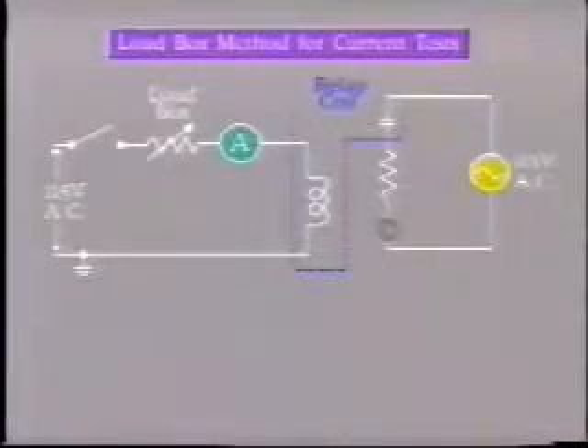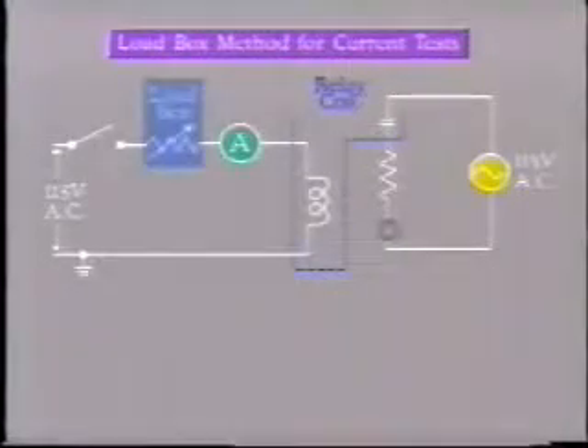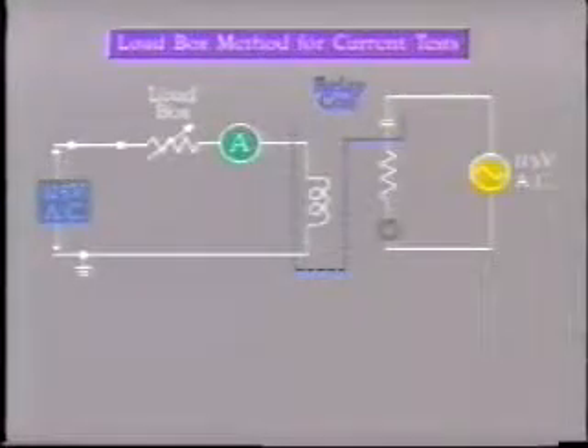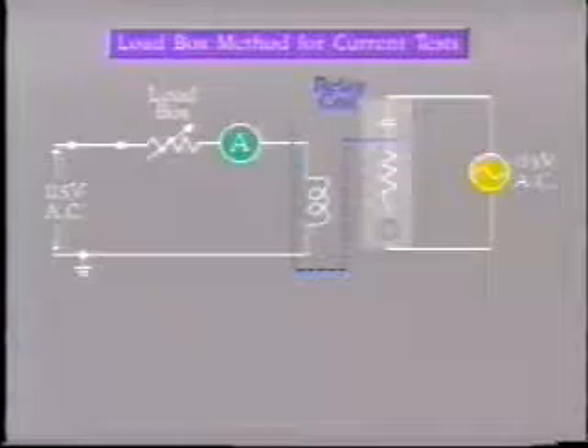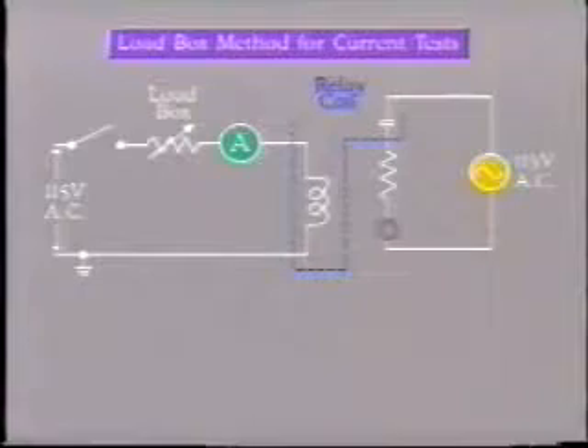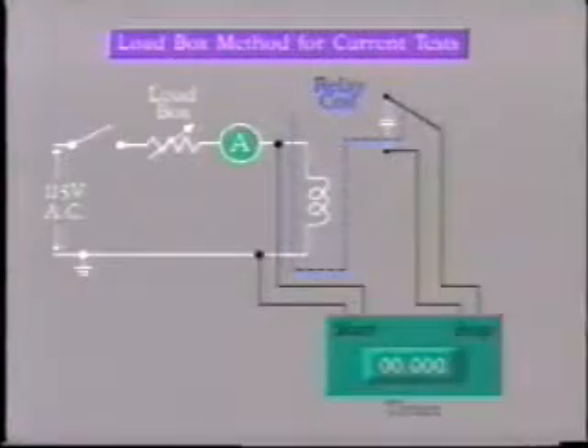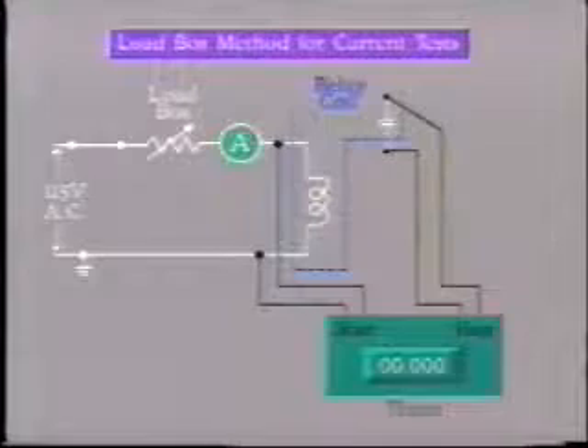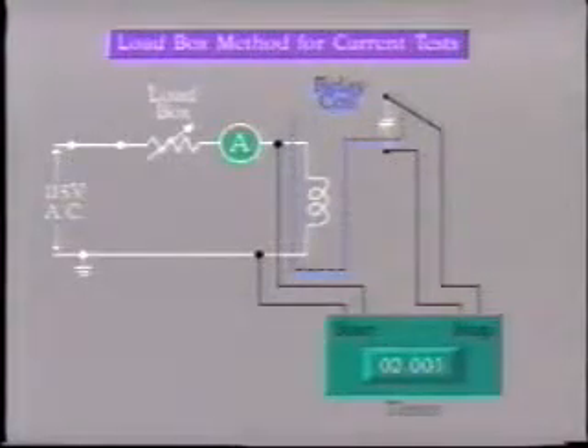First, variable current sources. A traditional method used to measure the pickup of an overcurrent relay is to connect a variable resistor called a load box and an ammeter in series with the relay, and to feed this from the station service 115-volt AC source. The relay's output contact is monitored by an indicating light. For time overcurrent tests, we can replace the indicating light by a timer, which is started upon relay energization and stopped by the relay's contact closure.